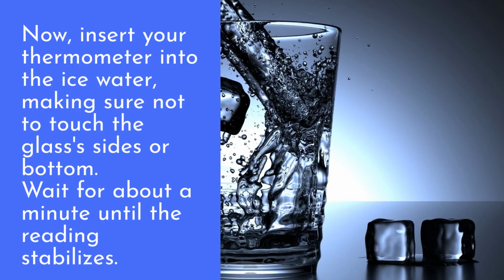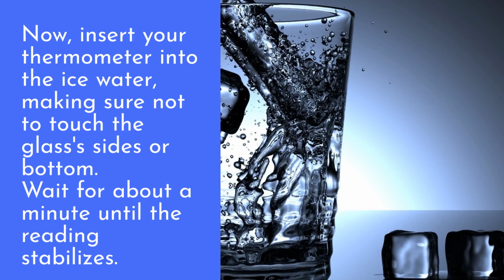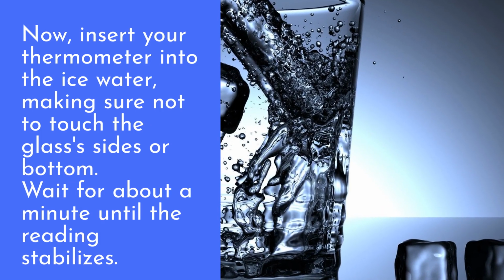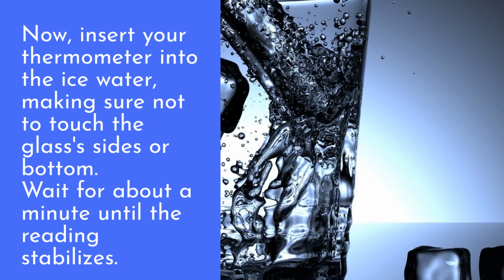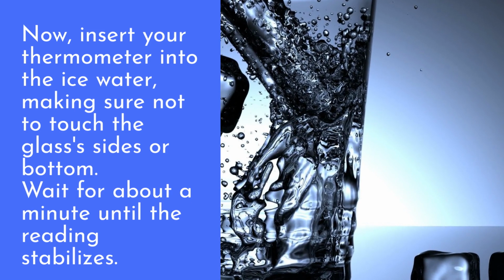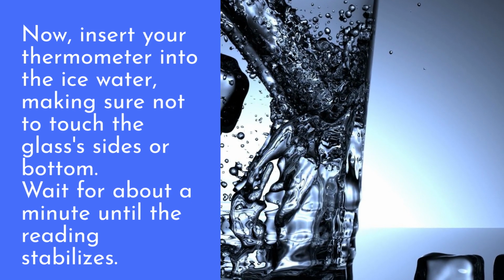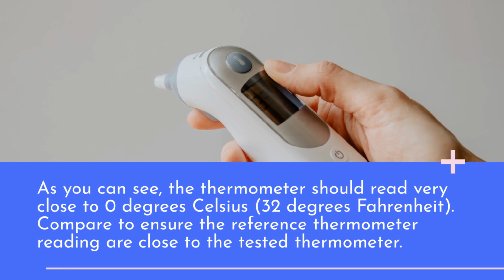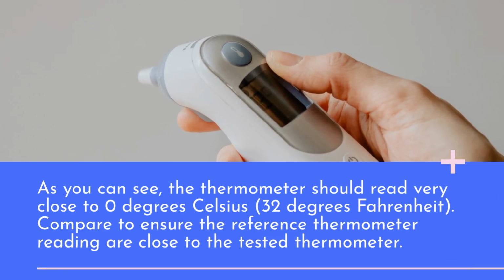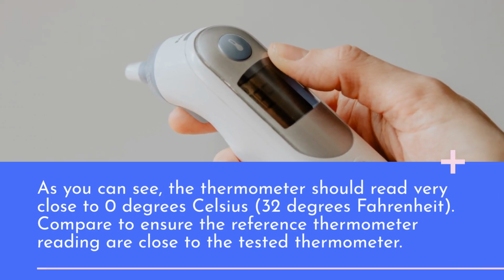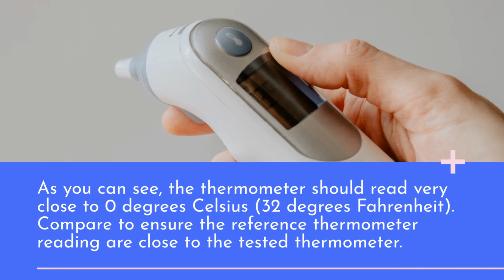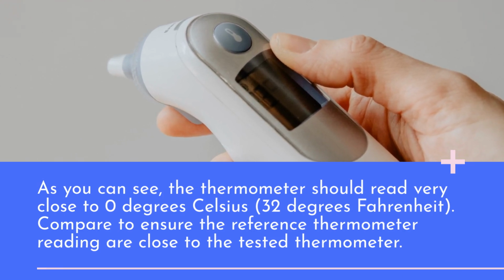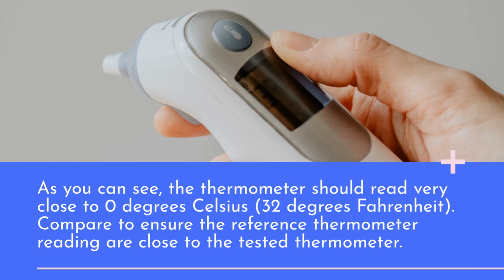Now, insert your thermometer into the ice water, making sure not to touch the glass's sides or bottom. Wait for about a minute until the reading stabilizes. As you can see, the thermometer should read very close to 0 degrees Celsius, 32 degrees Fahrenheit. Compare to ensure the reference thermometer readings are close to the tested thermometer.